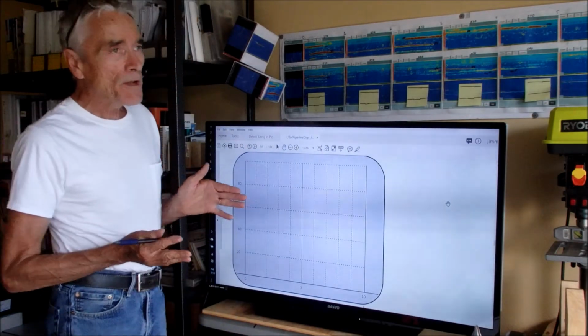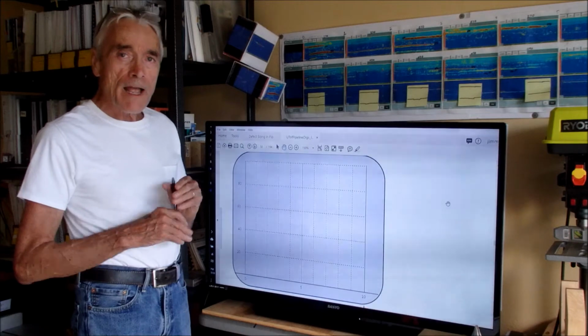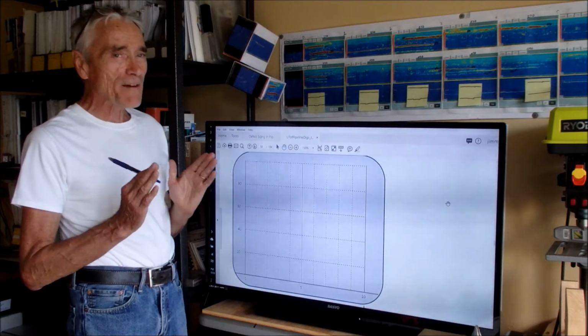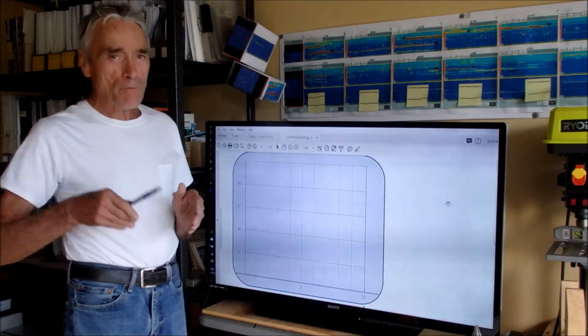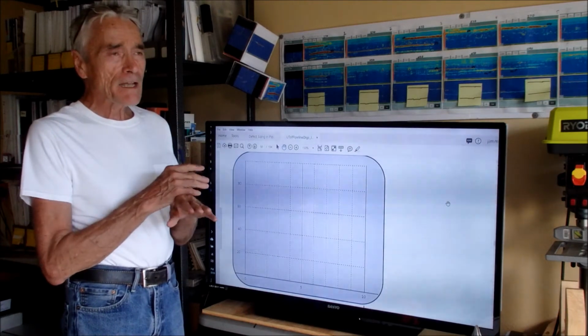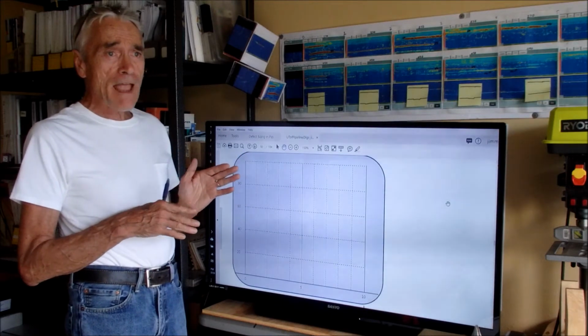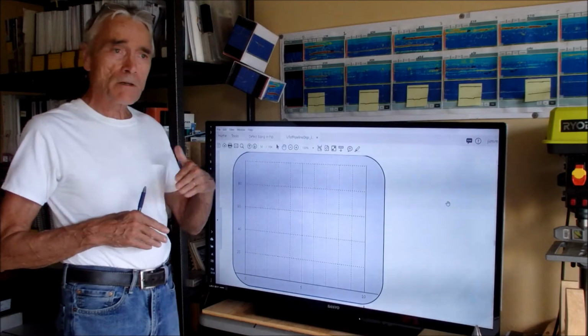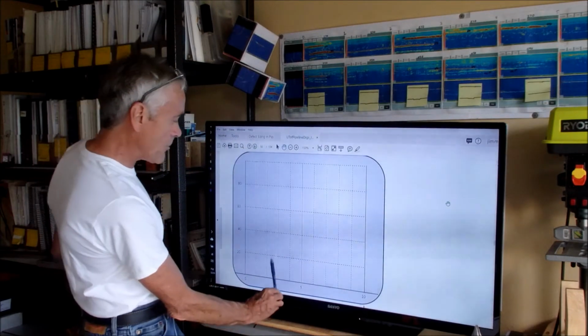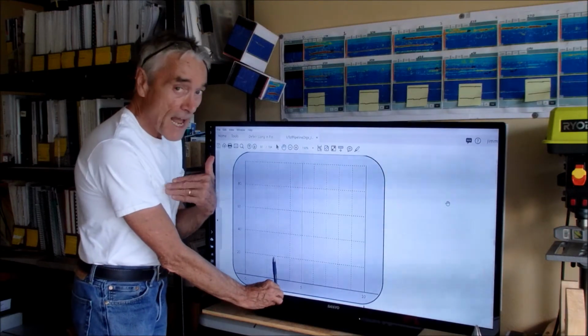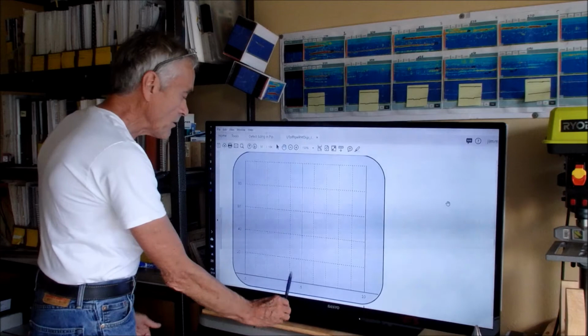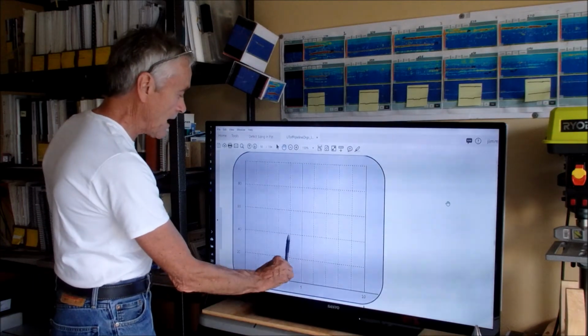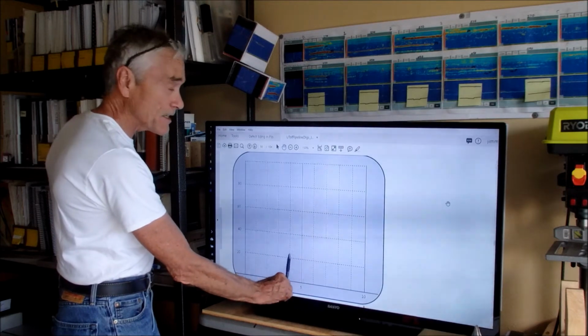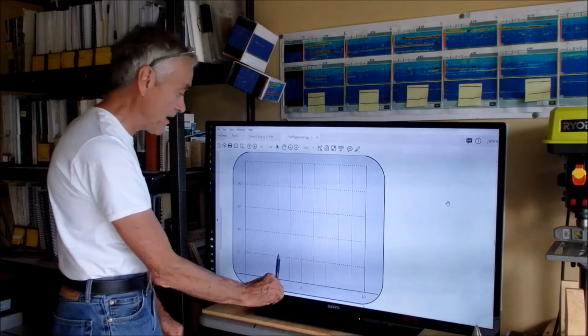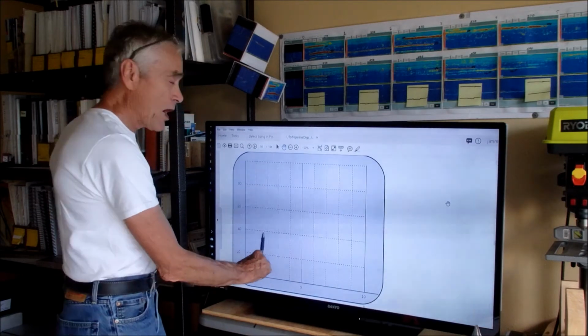I made a couple of attempts at it, and it was difficult to make sense out of it because we had a video earlier where we described how a 60 does not like to reflect out of a corner. Actually, if you've watched the previous video, a 60 has almost no reflection out of a corner, but some of the angles close to 60, like in the lower 50s or higher than 60, do. So like if you have a 300 deep corner trap signal, like all the notches on our notch block, when you're using the 60, it won't want to peak up at 300 deep. You'll have some angles higher than 60 where it will peak up and some angles lower than 60 where it will peak up.